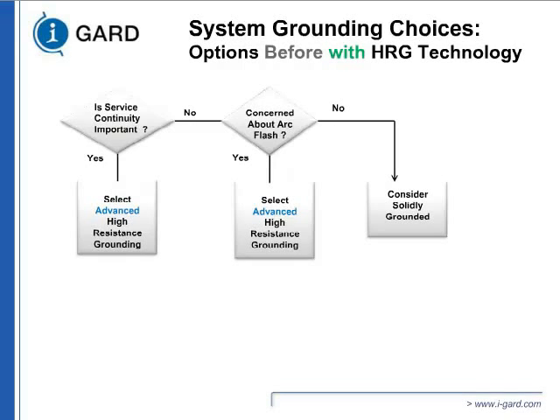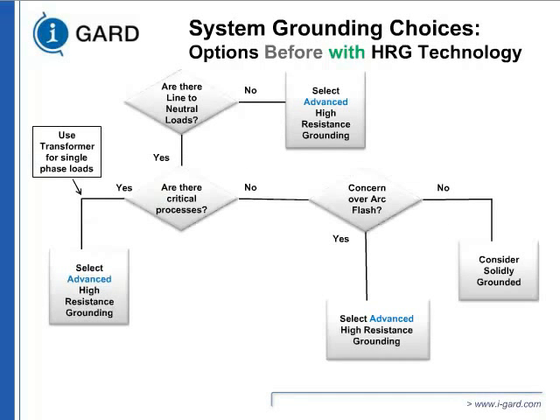Now this builds on that. One of the disadvantages of high-resistance grounding is that you cannot use phase-to-neutral load. So if your question is, what if I do have one? My system is not that clear. You still use a high-resistance grounding system for the critical process, but for single phase loads, you put in a smaller transformer. When I go to audits at sites, I'm so scared to see electricians using 277/480 volt lighting or 120/208 lighting coming from the main transformer. For discussion's sake, if it's a 1000 kVA transformer, you have close to 30,000 amp fault. If an arc flash happens, you're going to have a tremendous arc flash.